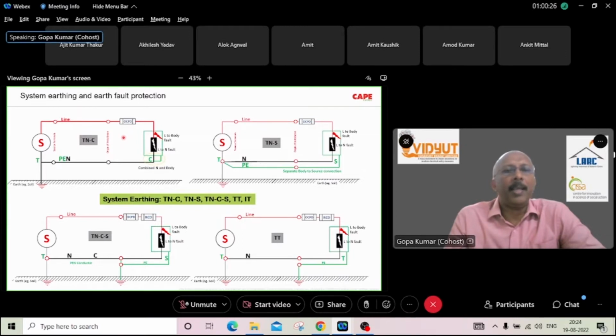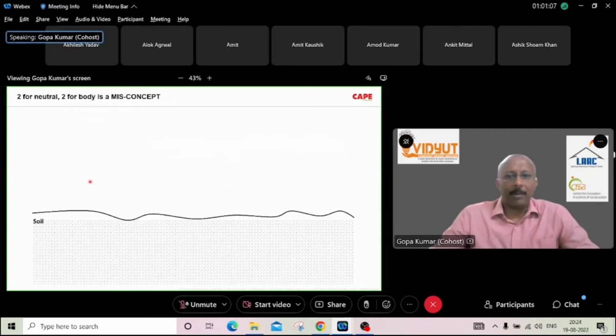There are different techniques with which the electricity can be taken from the electricity supply from the transformer and consumed in the electrical installation. And the important subject is called system earthing. System stands for the source, distribution and your connected load. It is classified into TN-C, TN-S, TN-C-S, TT, and IT. Unfortunately, even though our standards such as IS 3043 and IS 732 have very beautifully explained these systems and their application, most of the time this is a big confusing subject to the customer or to the engineer.